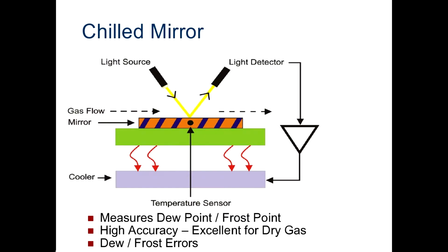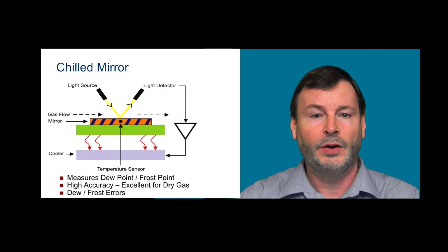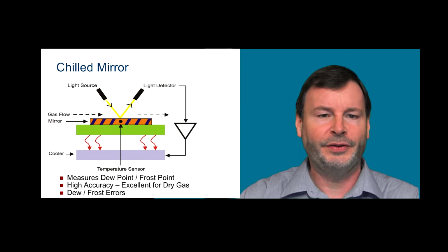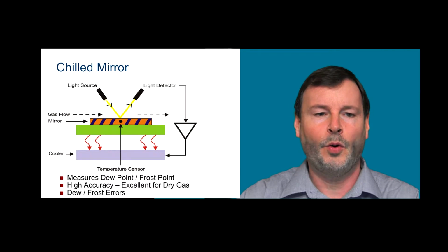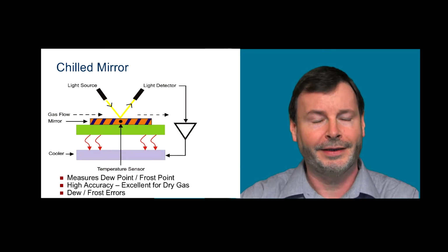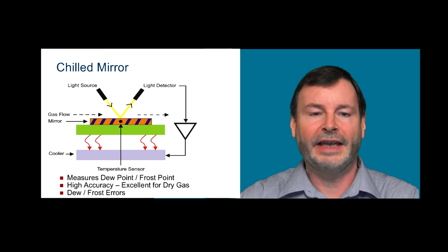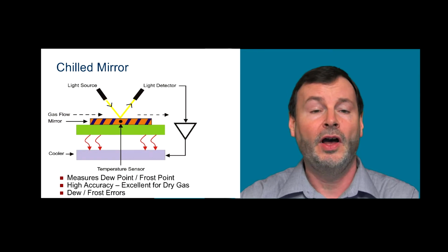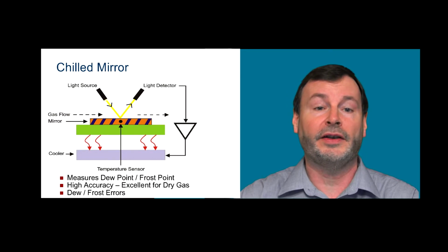In order to obtain a relative humidity value from a dew point hygrometer, one first must know, is the mirror covered with dew or is it covered with frost? And this brings a very common question, and that is, at what temperature does water freeze? Well, I used to think it was 0C, 32F. The true answer is water freezes at any temperature it feels like it. It will often supercool. It's not uncommon to see liquid water present at minus 30 degrees C on a chilled mirror hygrometer, particularly when things are clean and pure.